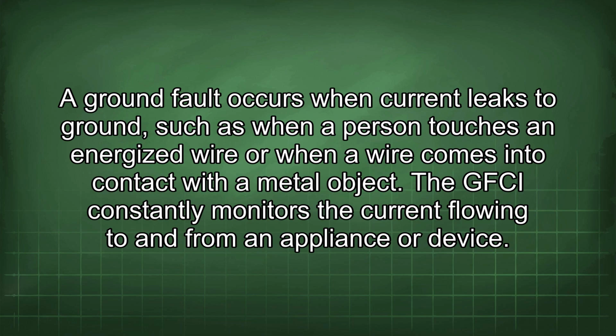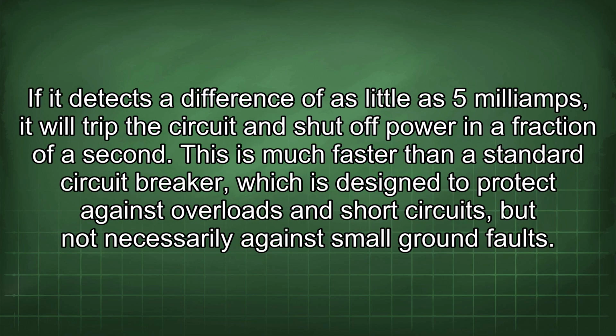The GFCI constantly monitors the current flowing to and from an appliance or device. If it detects a difference of as little as 5 milliamps, it will trip the circuit and shut off power in a fraction of a second. This is much faster than a standard circuit breaker, which is designed to protect against overloads and short circuits, but not necessarily against small ground faults.